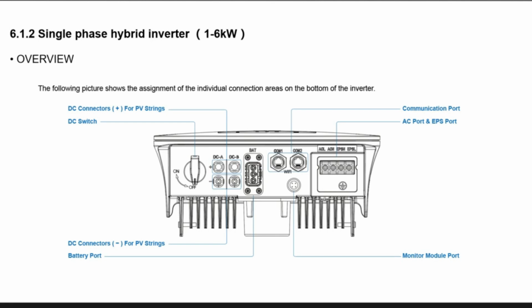I'd always recommend that you did your wiring first on the bottom for your AC and for your essential circuit supply, and also your data cable link before you actually hang it on the wall. It's much easier to wire it up and then put a cover over it, make your cables off to the length that you actually require, swing it round, and then you can hang it on the wall much easier, and then connect it to your AC isolator. That's just a tip for everybody. It's much easier to do it that way around.